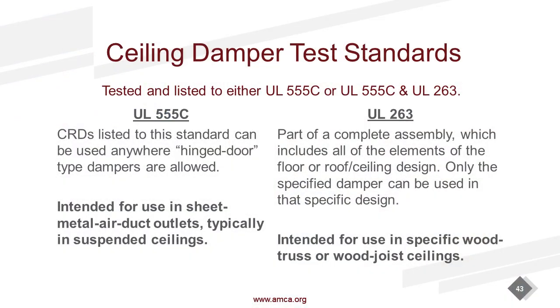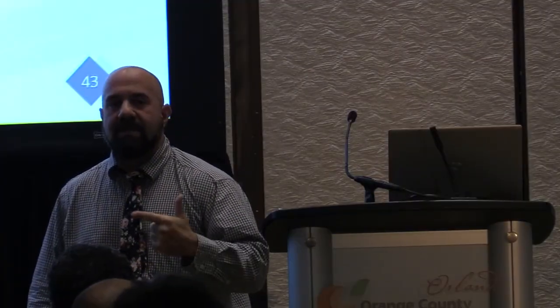Then it gets even more confusing, something we'll dip into at 3 o'clock a little more. There's two different types of ceiling radiation dampers. There's those intended for use where hinge door dampers are allowed. That's your fire-rated T-bar ceilings with the steel truss rated up to 3 hours, most common application. Then you have very specific floor ceiling assemblies that have a specific manufacturer's damper tested. That's our wood truss and wood joist, multifamily. Those assemblies are very specific as to what damper is approved. Substitutions are not allowed in those tested assemblies. Again, if that just piqued your interest, come back at 3 o'clock.